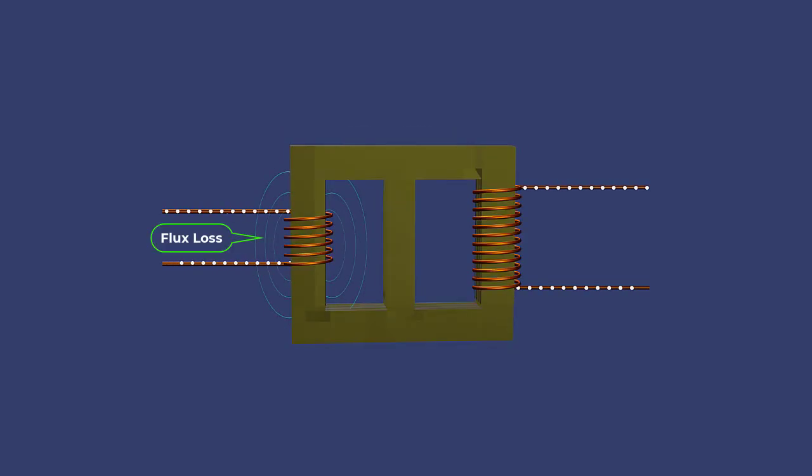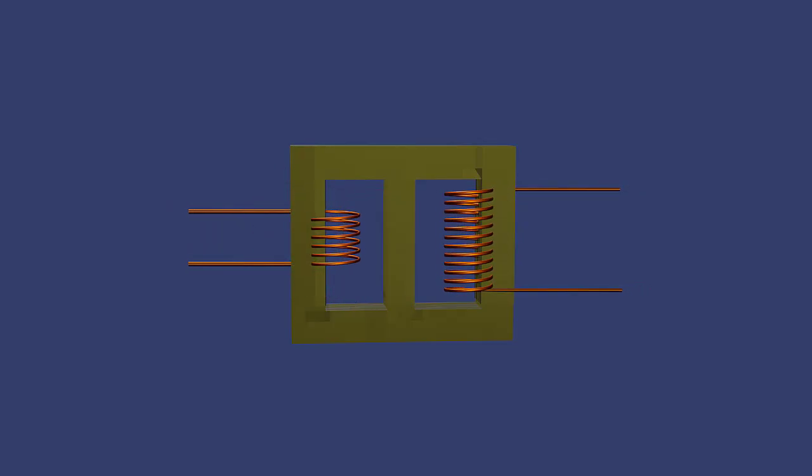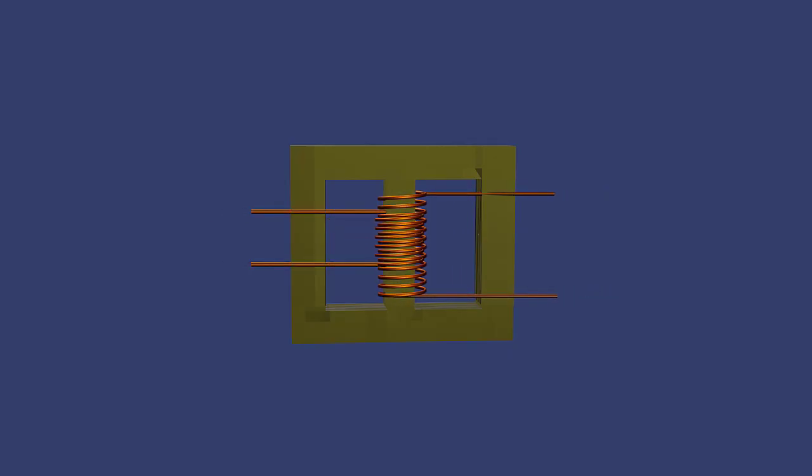Flux loss typically refers to leakage flux, which is the portion of the magnetic flux that does not link both the primary and secondary windings. Winding the primary and secondary coils one over the other helps to reduce leakage flux and improve coupling between the coils.